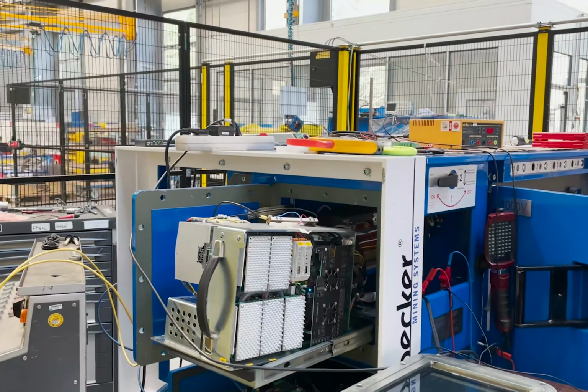In the high voltage testing area, there are other equipment available. Here's a 15,500 volts transformer, 500 kilovolt ampere with taps where the voltage is controlled via the control panel. The surge test generator can go up to 100 kilovolts. The current generator goes up to 30 kiloamps for short circuit tests. It is for low voltage tests only. For high voltage and high current requirements, we work with specific external laboratories such as Siemens Germany, Schneider France, or KEMA Czech Republic.